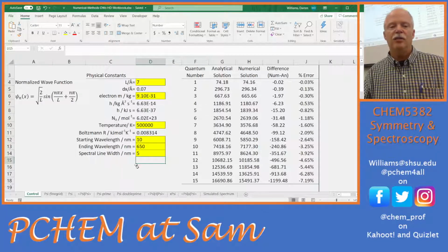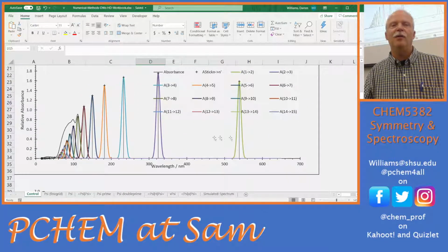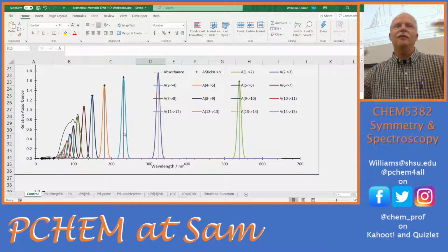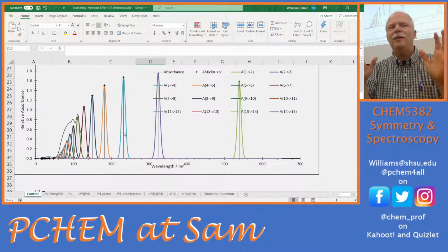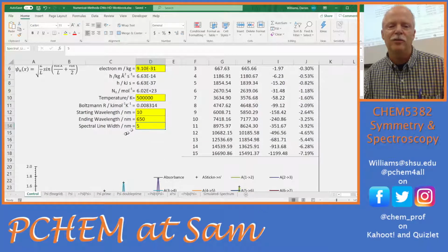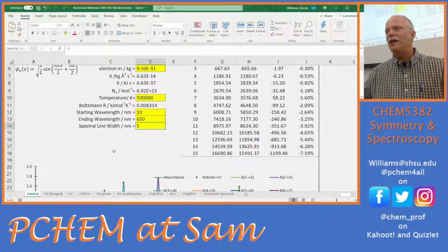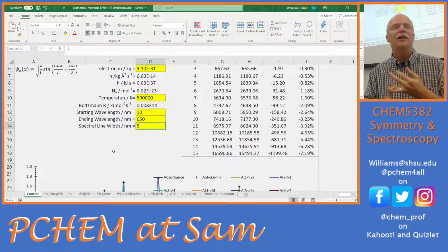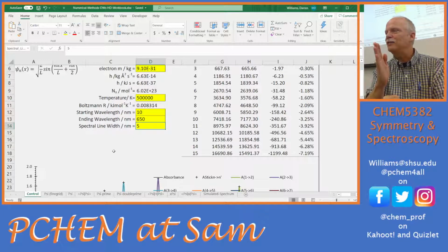Yeah. And so what you'll probably find is that your spectrometer won't be the thing that limits your resolution. It'll be the molecules themselves, and like I said, the random environment. So let me put a caveat on what I've been saying. Let's say this is the spectrometer resolution or spectral line width, but that may not be limited by your spectrometer, but by your molecules. So if you have an amorphous sample, it's going to have wider peaks than a crystalline sample. Think about all the molecules in a crystal. They have the same environment, so they have the same transition wavelengths.